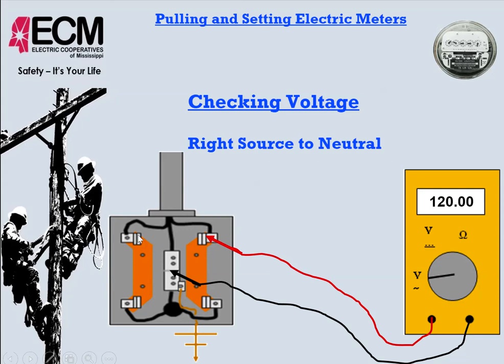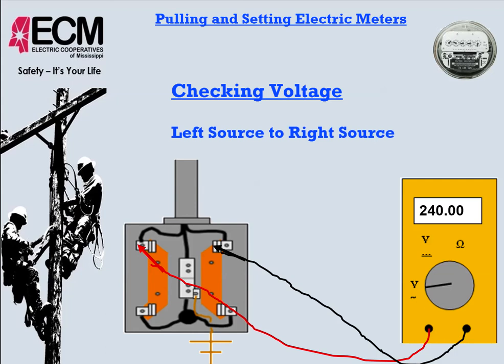So we know that our two hots are at the top and our neutral is in the middle where it's supposed to be. And we can double check and verify that by testing across the top and getting a potential difference between the two line side lugs of 240 volts. Okay, this would be the hots where they're supposed to be, the neutral where it's supposed to be, and also making sure that we have the proper voltage.